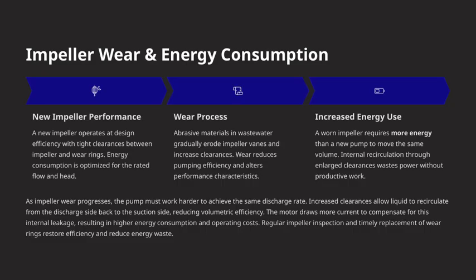Let's talk about impeller wear and how it impacts energy consumption. When a new impeller is installed, it operates at its optimal efficiency, thanks to tight clearances between the impeller and the wear rings. This means it uses energy effectively for the rated flow and head, ensuring everything runs smoothly. However, over time, abrasive materials in wastewater gradually erode the impeller vanes. This wear increases the clearances, which in turn reduces the pump's efficiency and can change its performance characteristics. Essentially, the pump isn't working as effectively as it should.